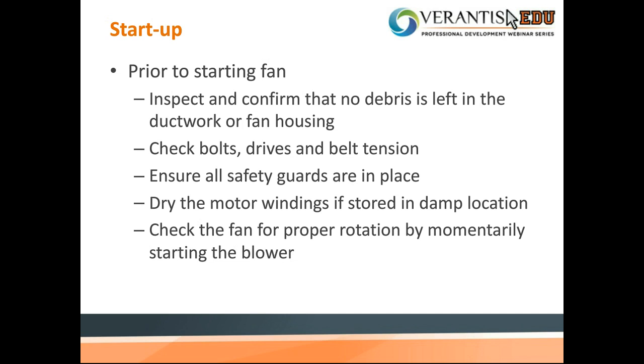Ensure all safety guards are in place. So make sure your belt and shaft guards are ready to go. Your canopy is tightened down. We want to make sure everybody working on a fan is safe. Dry the motor windings if it's stored in a damp location. And then check the fan for proper rotation by momentarily starting the blower. Like I said, that goes back to making sure your motor is wired up properly. We want to make sure it's spinning in the right direction.